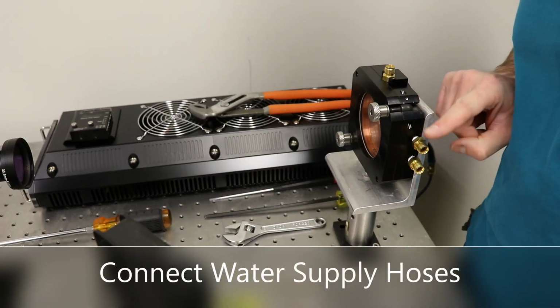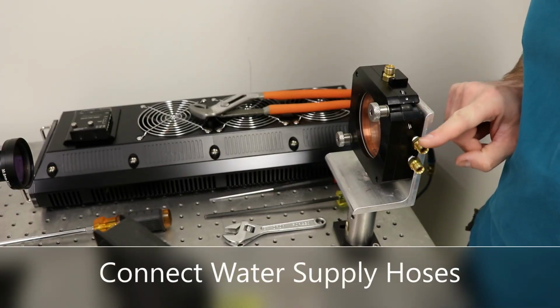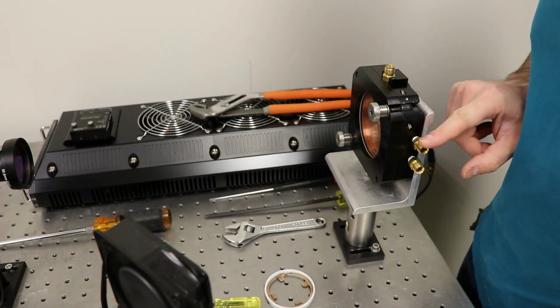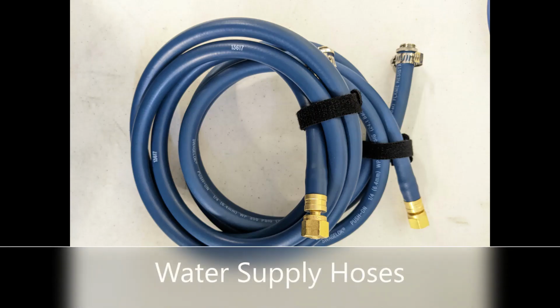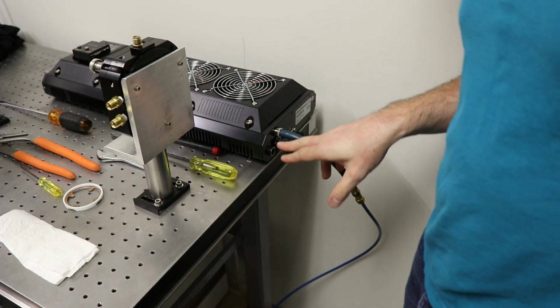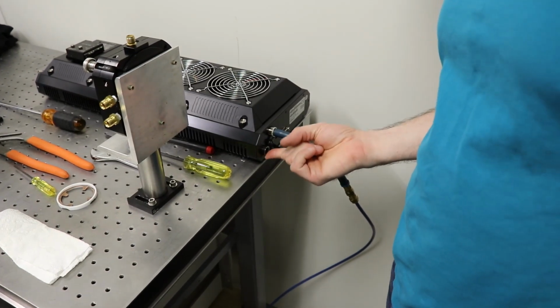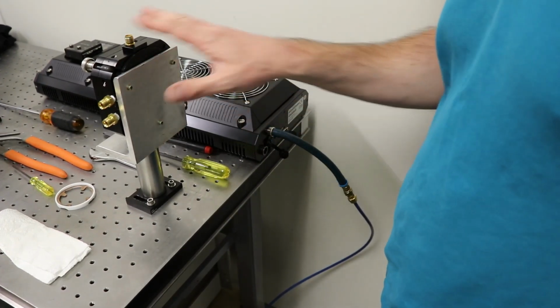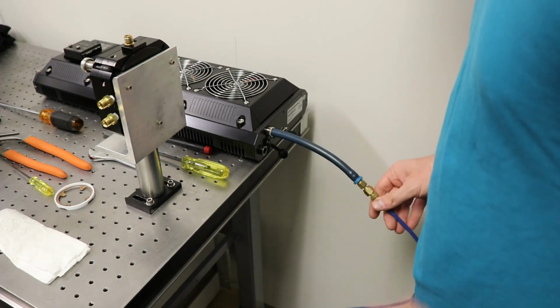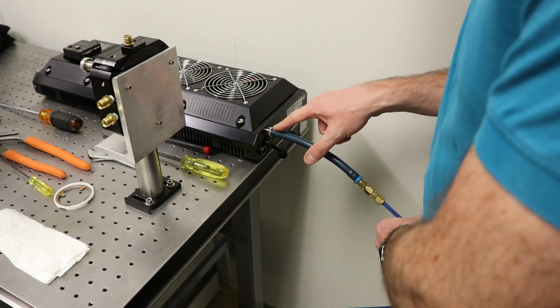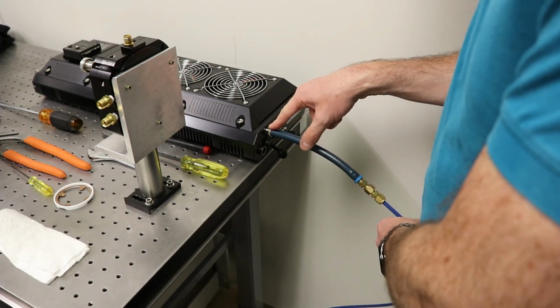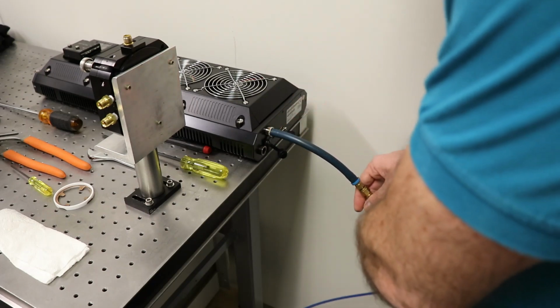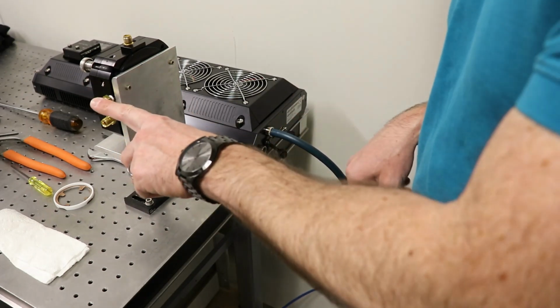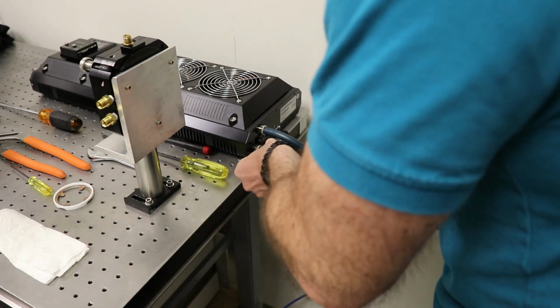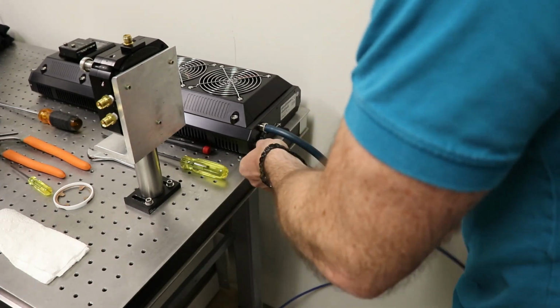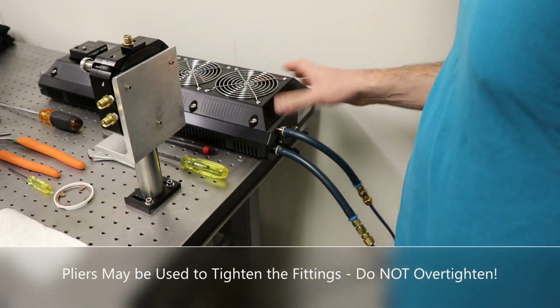Next, we will mount the water connections from the water circulation unit. There's an inlet and an outlet for the water to flow from the cooler to the cell. Cables are provided with mating connectors to connect to these connections on the cooling unit. These cables then attach directly to the cell. Check your system that it doesn't leak water once it's turned on.